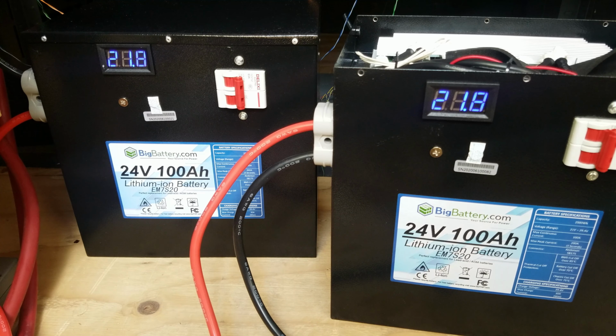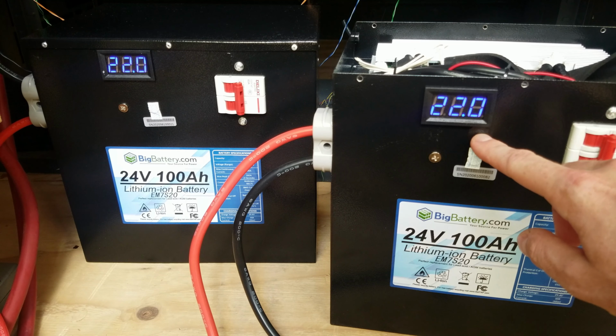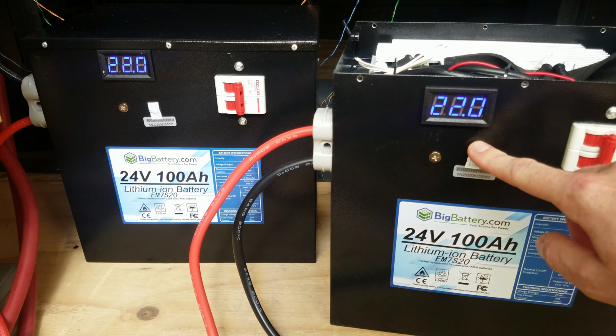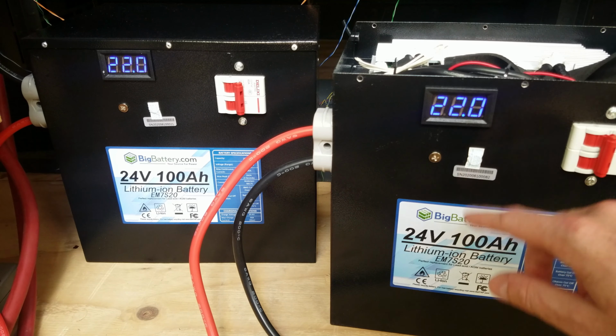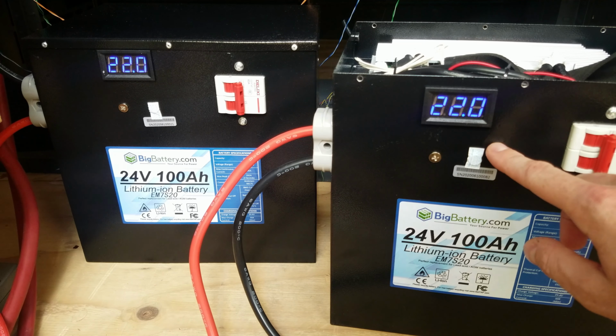And the inverter has shut off. So the load disconnect on the inverter triggered around 21, so what was that, 42 volts? That sounds about right. So we know that the 45-ish amps this inverter was putting on here did cause about 1 volt of voltage sag. However, I would consider that very normal. That wasn't bad at all.